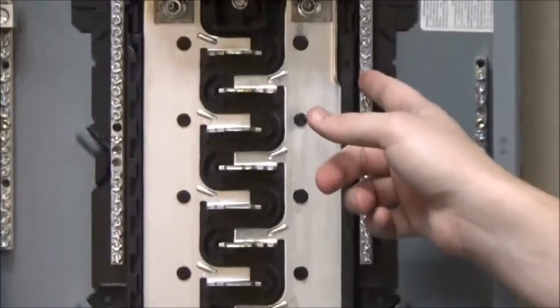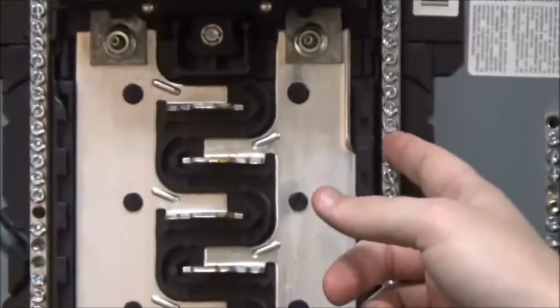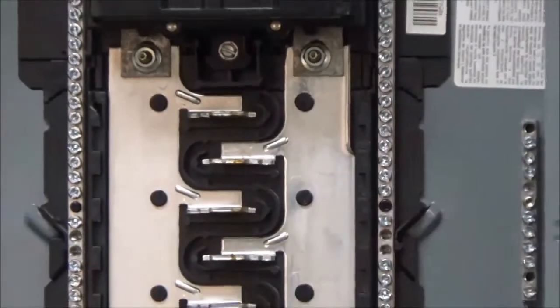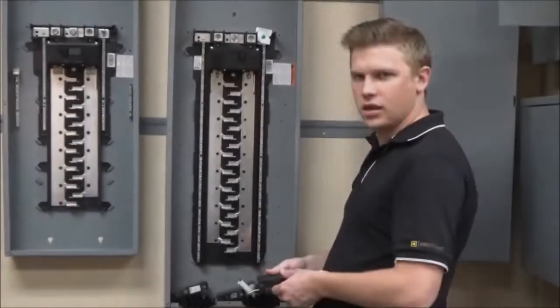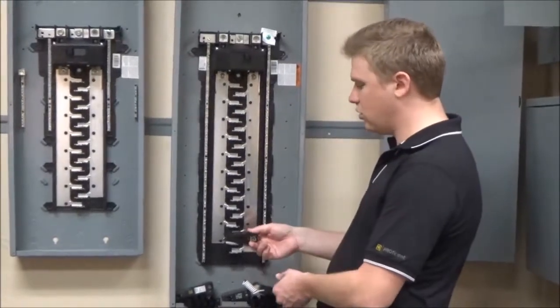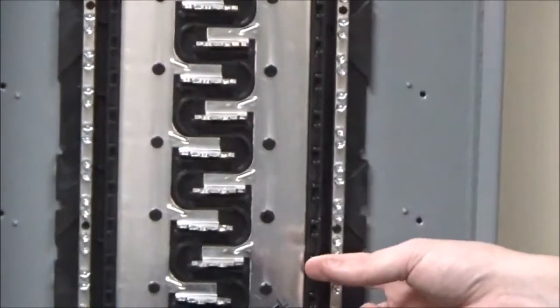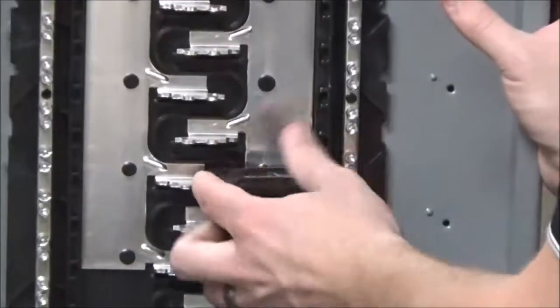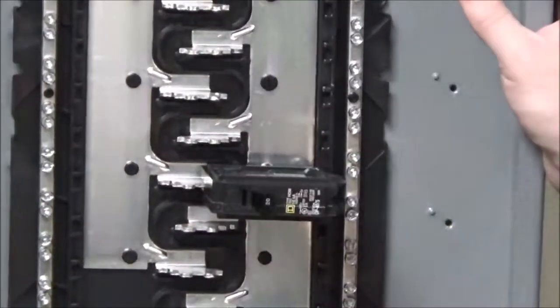To install a standard Homeline plug-on breaker, you would slip this tab into the notch and then rock forward to attach it to the bus. The same method is used on the standard panels.